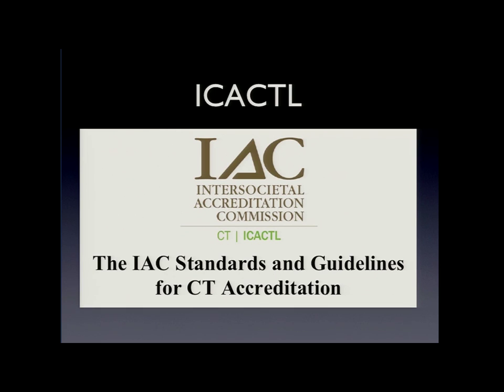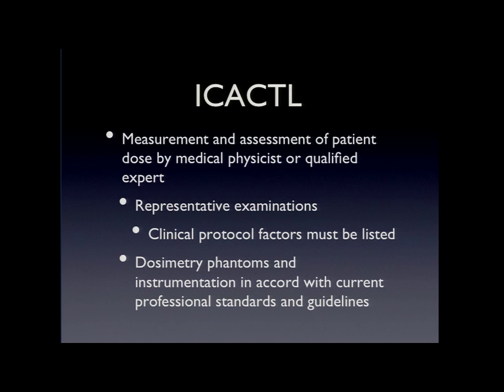The IAC has its standards, and you can just go to the website and download them. The thing to note is it says that you need to measure dose in some aspect. The qualified medical physicist needs to do this and evaluate clinical protocol factors. And these factors must be listed on the report so that you're identifying, as Keith was saying, what are we doing?